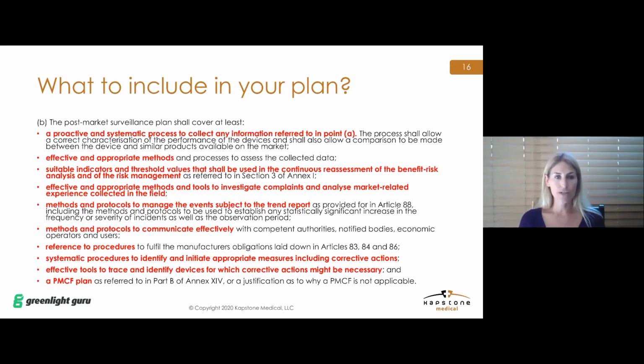The plan also needs to have a reference to procedures to fulfill manufacturer obligations, systematic procedures to identify and initiate appropriate measures, effective tools to trace and identify devices for which corrective actions might be necessary, and then your post-market clinical follow-up plan. So although this is establishing for you what is required in that plan, there's no issue with referencing existing procedures and existing methods on how these are managed within your organization. But if they do not exist or specific to a device, you do need to have them specifically in your post-market surveillance plan.